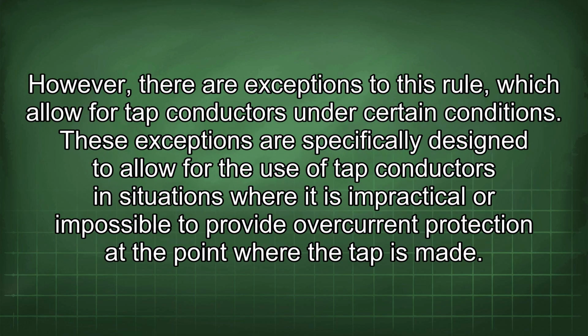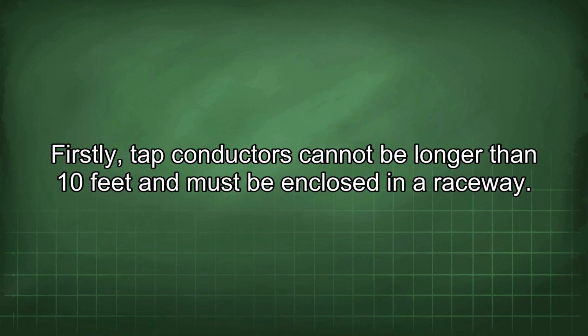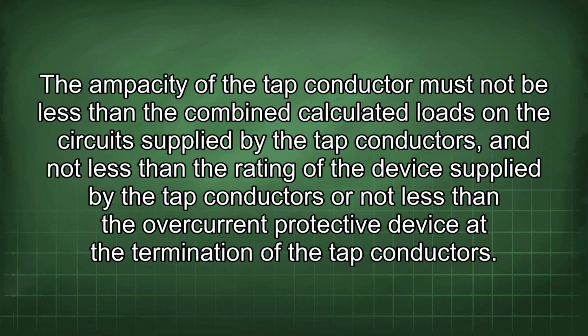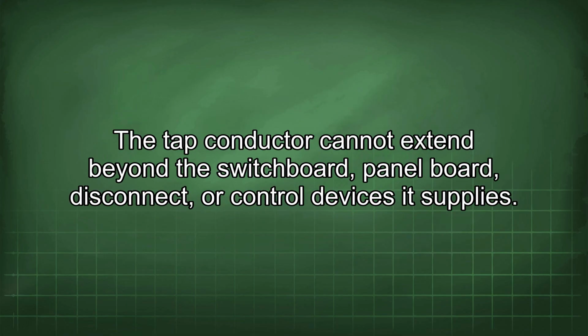However, there are exceptions to this rule, which allow for tap conductors under certain conditions. These exceptions are specifically designed to allow for the use of tap conductors in situations where it is impractical or impossible to provide overcurrent protection at the point where the tap is made. Firstly, tap conductors cannot be longer than 10 feet and must be enclosed in a raceway. The ampacity of the tap conductor must not be less than the combined calculated loads on the circuits supplied by the tap conductors, and not less than the rating of the device supplied by the tap conductors, or not less than the overcurrent protective device at the termination of the tap conductors. The tap conductor cannot extend beyond the switchboard, panel board, disconnect, or control devices it supplies.